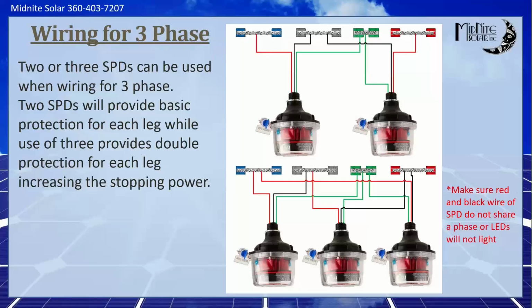Or if it's a real high value item and you want to just add a little extra protection, you go ahead and use 3. When you're using 3, though, make sure that you actually put the red and the black lead to separate phases, or you will not get an LED. So, red of 1, black to the second phase, and so on. Just go ahead and add that, like that. A common one that I've seen is the big Bergey three-phase wind turbines. People like to put 3 on because the Bergey is fairly expensive and getting protection makes sense. So they will cover three-phase up to 480 volts AC. You can use the SPD 600 for 480 three-phase AC, or the 300 AC for 208 three-phase. So if you're doing a 3 stack of Rosies for 208 three-phase, go ahead and use 3 of them.